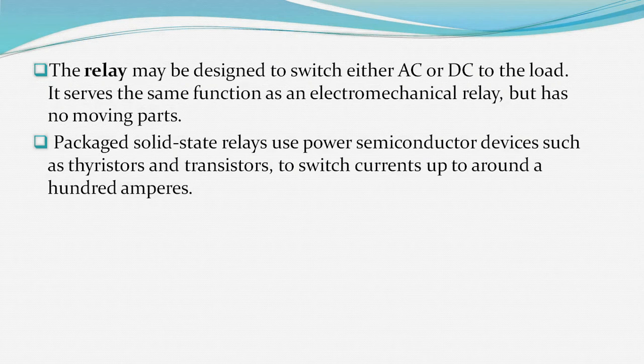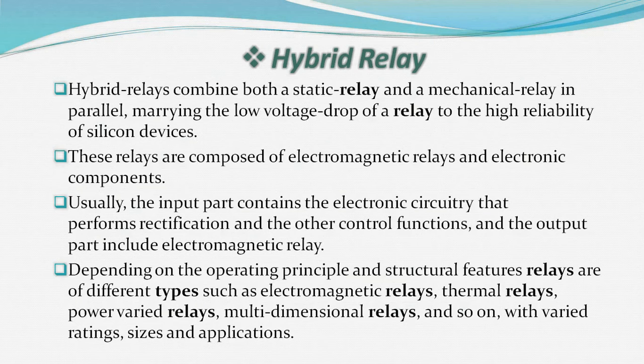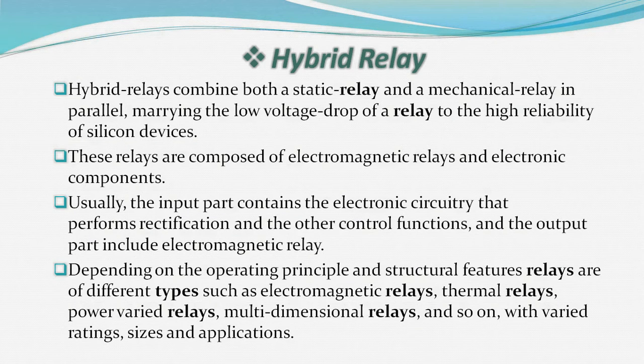Packaged solid state relays use power semiconductor devices such as thyristors and transistors to switch currents up to around 100 amperes. Hybrid relays combine both a static relay and a mechanical relay in parallel, marrying the low voltage drop of a relay to the high reliability of silicon devices. These relays are composed of electromagnetic relays and electronic components.